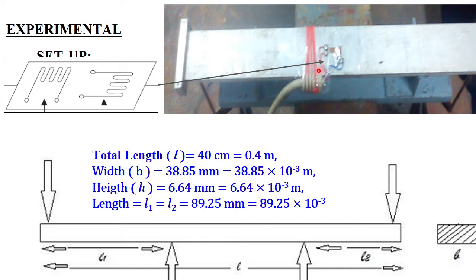Some wires are connected, and for the 4 strain gauges we will get 8 such wires. Okay. So these wires are now coming out through this one. This one contains those wires. You understand the sealing here, the sealing is applied on these strain gauges.